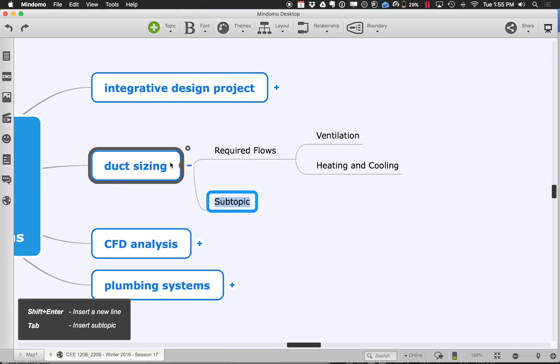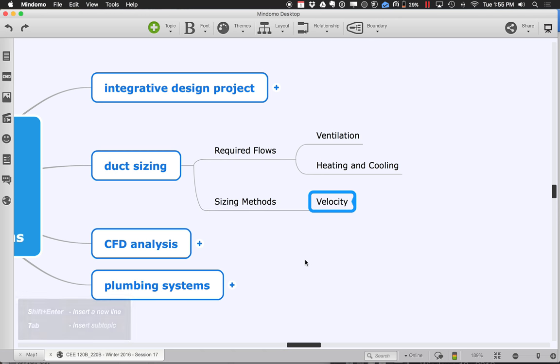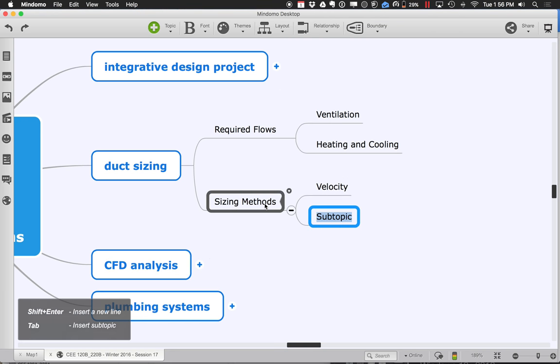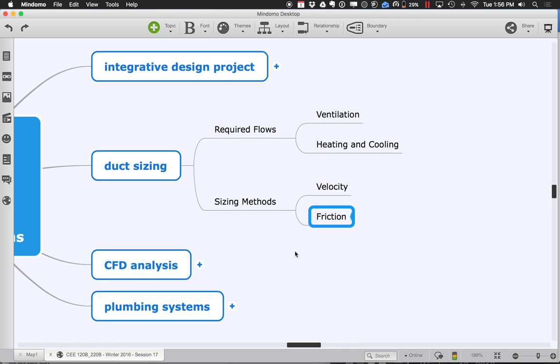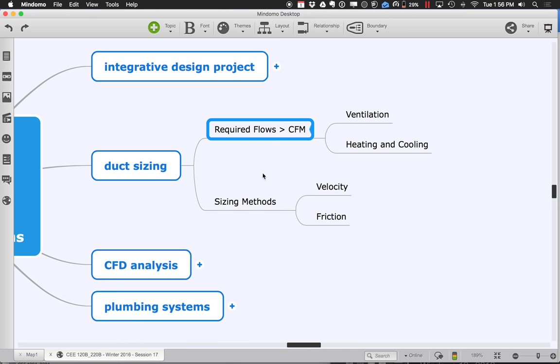There are different methods for sizing ducts. One approach uses velocity as the restricting criteria — there's a certain amount of flow, and we only want the speed to go up to a maximum level. If it gets too fast, you get problems with noisy ducts or static electricity being generated. Gustavo, do you have guidance on sizing methods? Did you use velocity in your tutorial? — Yes, it was based on velocity. That seems to be the easiest to understand.